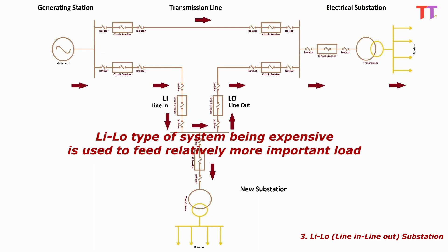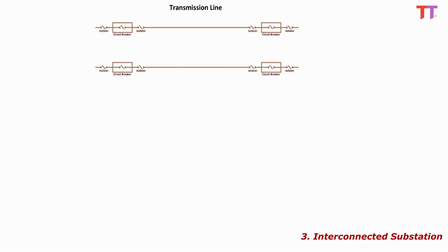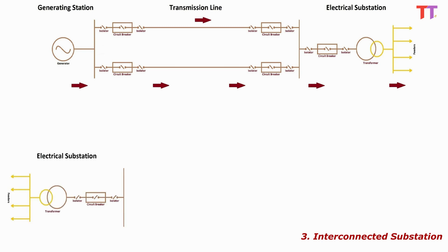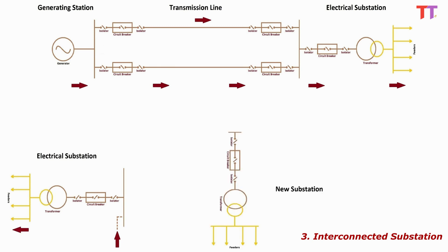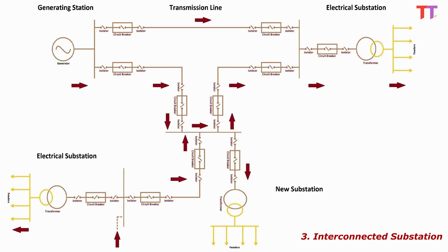Hence such a system, being expensive, is used to feed a relatively more important load. 4. Interconnected substation. In this type of layout, a substation is connected to multiple power sources. Consider an existing transmission line connecting two substations transmitting power in this direction. Also consider one more substation connected to other generating stations or lines and feeding its connected load. A new substation is constructed nearby. From the existing line as well as the existing substation, power sources for the new substation are taken. Now in case of fault on any one of the lines, the other two lines continue to supply power. Also in case of breakdown of any two lines at the same time, the third line continues to supply power.